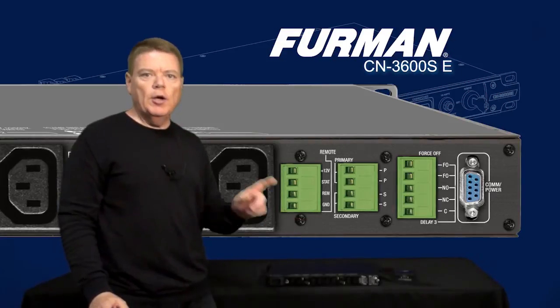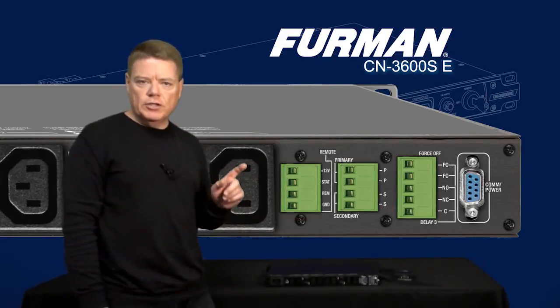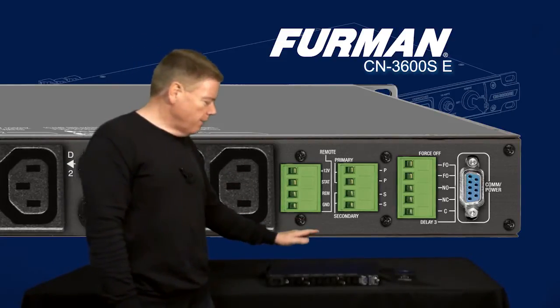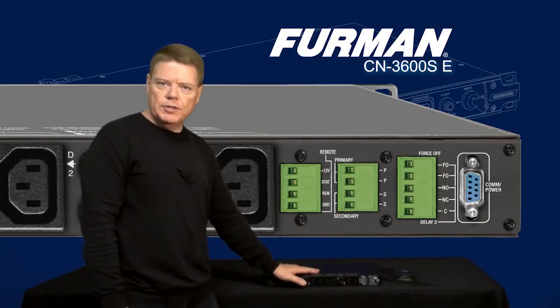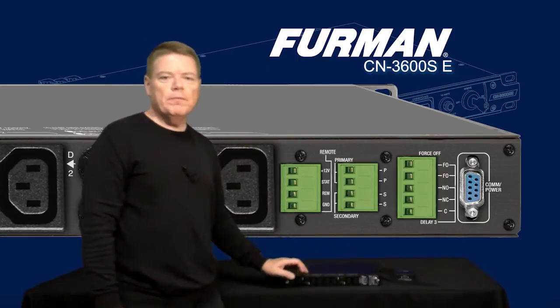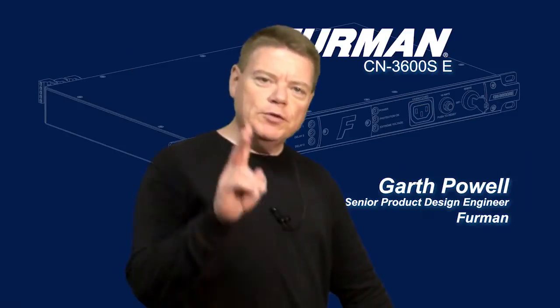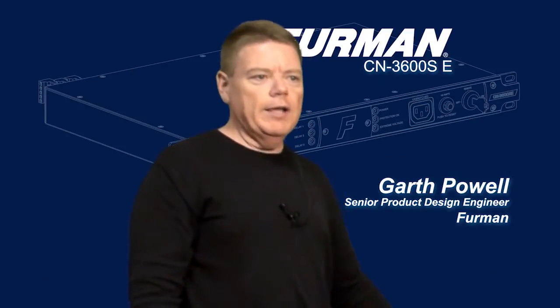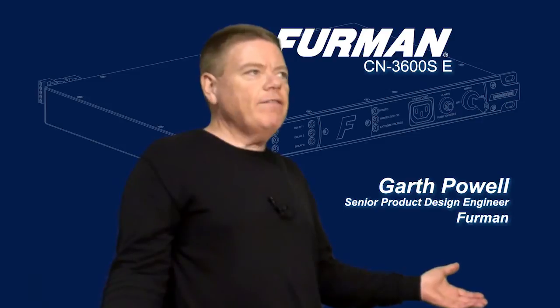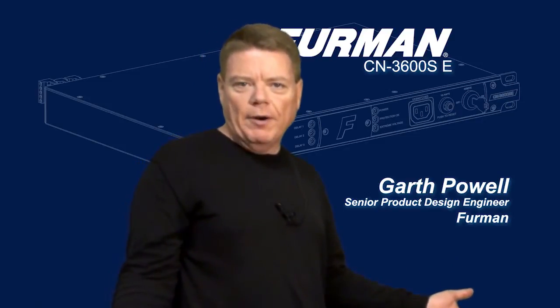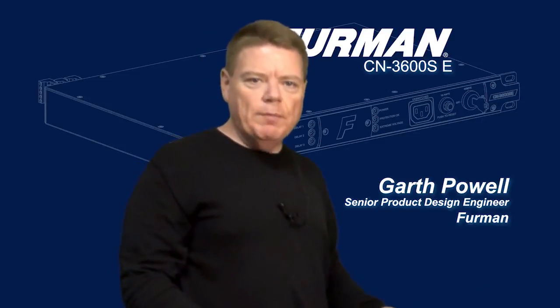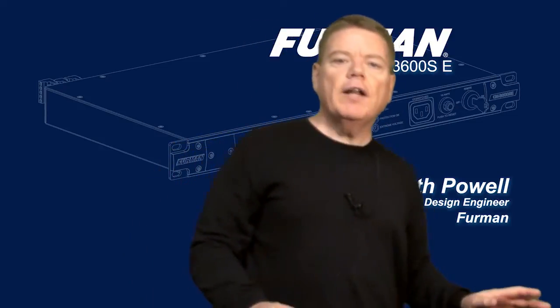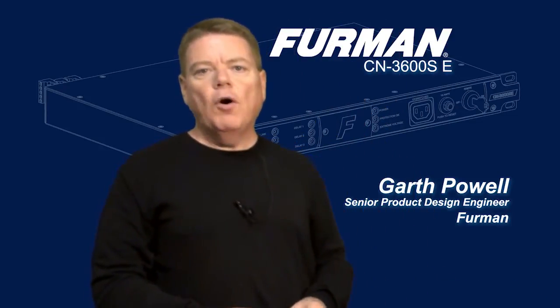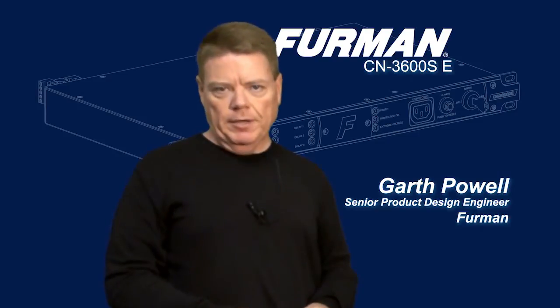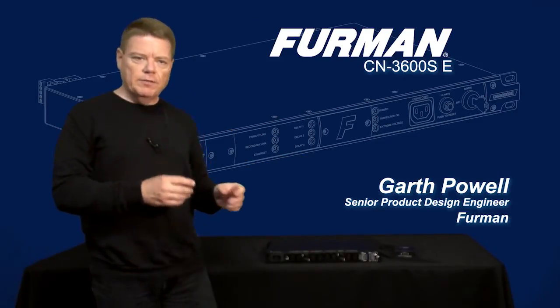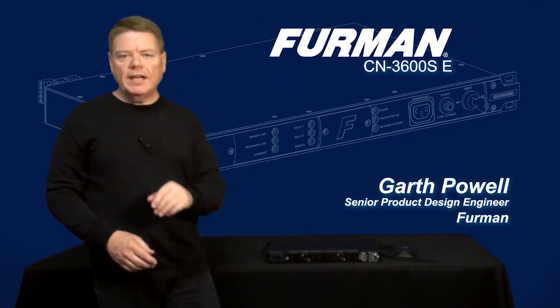You can have dry contact closure and use those as a secondary unit in the chain if you like. But here's where I'm going to encourage you to start anew and think about having the entire system be smart sequencing, because the second port is two-way communication, and with two small wires, as little as half millimeter, like a twisted pair wiring, now all of a sudden you have the means to communicate not 100 meters, but over 330 meters from unit to unit, from the primary unit to every secondary unit.